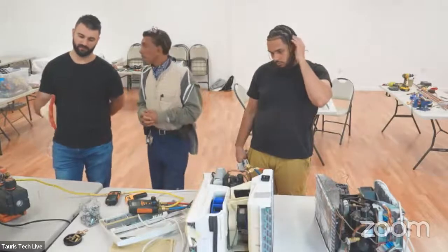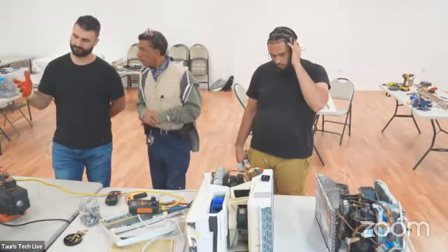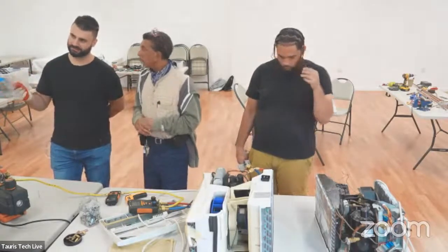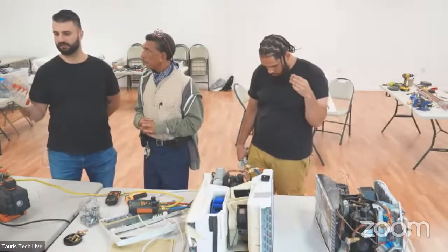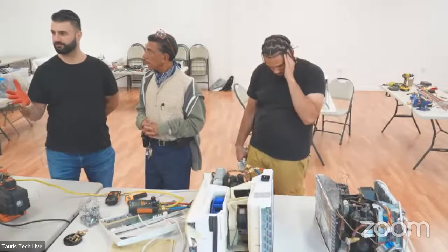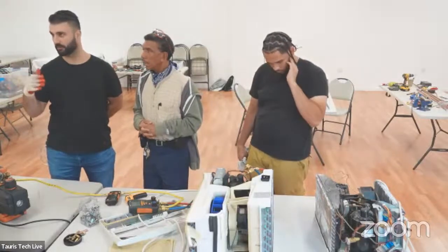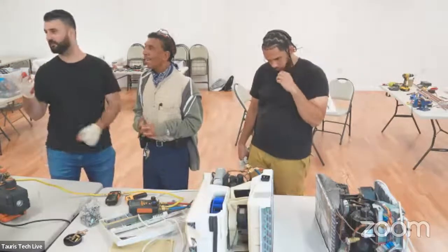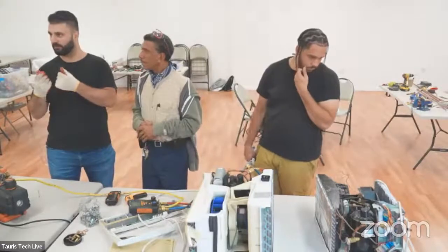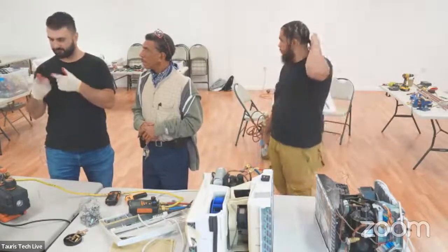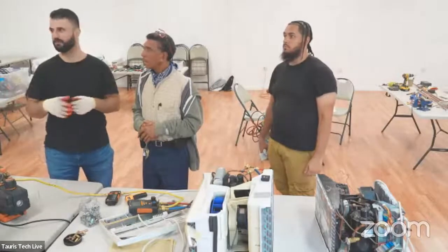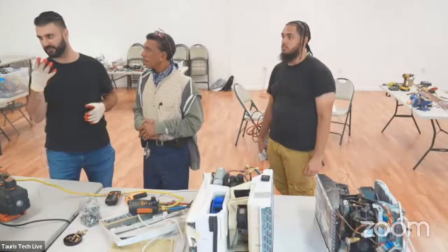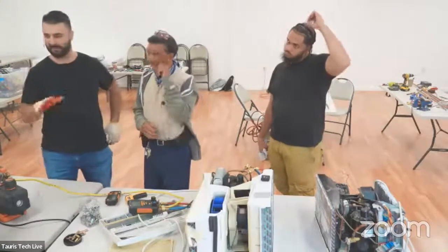So at my old job, we had a very old absorber, and it had a vacuum pump. You've got to have a vacuum pump. There was a leak on it, so we just kept it running for a really long time. And we could see that the moisture was mixing with the oil, turning it into water, so we were just dumping that. You could tell that the oil was bad.